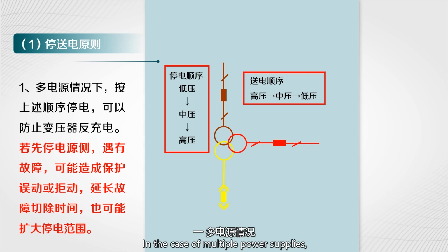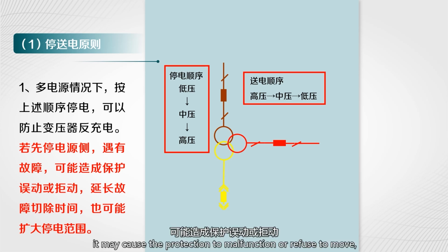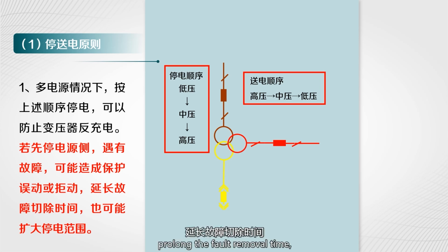In the case of multiple power supplies, the power outage in the above order can prevent the transformer from back-charging. If there is a fault on the power supply side first, it may cause the protection to malfunction or refuse to move, prolong the fault removal time, and may also expand the range of power outage.